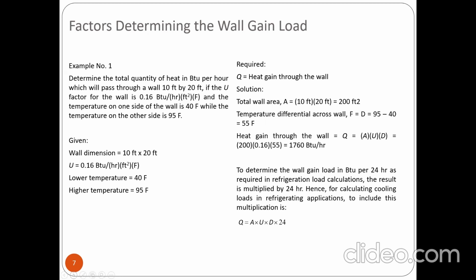So example number 1, determine the total quantity of heat in BTU per hour which will pass through a wall 10 feet by 20 feet, if the U factor for the wall is 0.16 BTU per hour square foot Fahrenheit and the temperature on one side of the wall is 40 Fahrenheit while the temperature on the other side is 95 Fahrenheit. Given the wall dimension 10 feet by 20 feet, U is 0.16 BTU per hour square foot Fahrenheit. Lower temperature 40 Fahrenheit, higher temperature 95 Fahrenheit. Required Q is the heat gain through the wall.